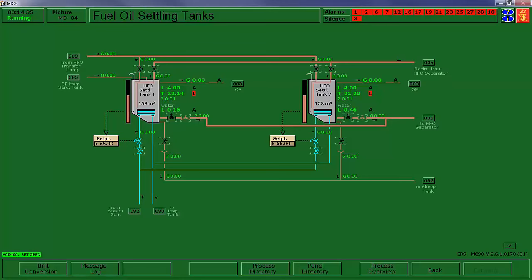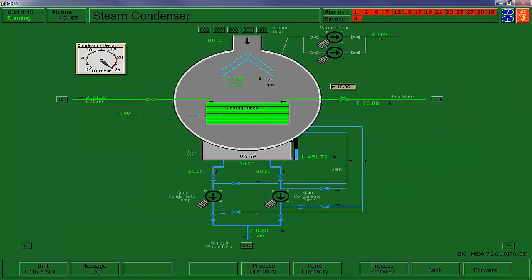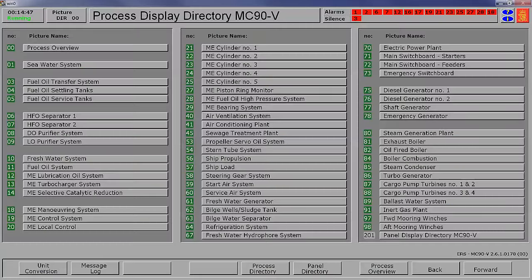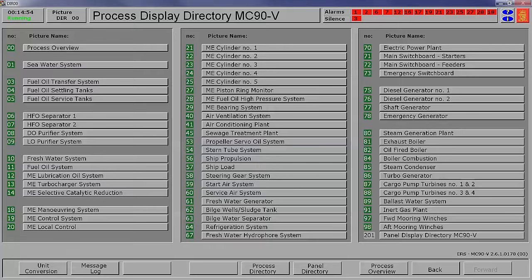Now in your storage tanks, if we go back, in these tanks, you would not really want to get above 50 because you don't want to produce that much vapor coming out of those tanks. But relatively, in your settling tanks, it's there for a much shorter period of time. All right, from the settlers, we will now go to our service tanks.